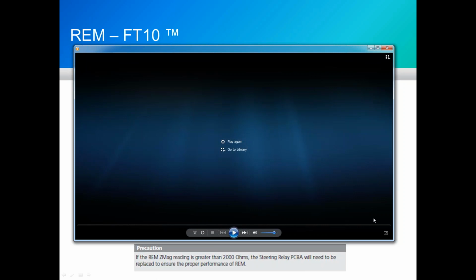So as I was starting to say before I went back to the test screen, that center screen used to be live in the Force Triad in the center display, but we never really paid a whole lot of attention to it. In this case, we are going to be using that screen, as you saw, for the REM test. There are two internal current transformers, primary and secondary, so we'll be able to see and compare what the generator thinks it's producing for current, power, and such versus what we're actually measuring. One thing to note is that the secondary measurement point is the closest to the output of the FT10.